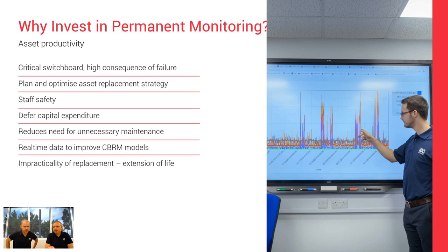So why do people install monitors? It really comes down to a number of different things. Critical switchboards, high consequence, which is what we've talked about. If you know that you're going to have to replace an asset soon, it takes time to get that done, and you're looking at extending the life during that period, so extending the life of the asset by de-risking it. Of course, staff safety, if you're working on one busbar and you've got the other one live, people are in that switch room for an extended period, people put monitoring on the other half of the switchgear. If you're looking to extend the life of the asset, then deferring capital expenditure is another driver behind this.